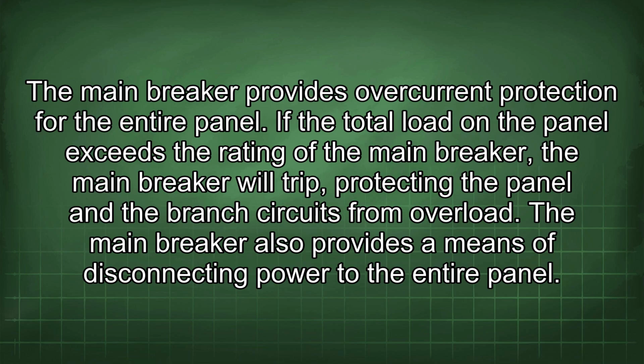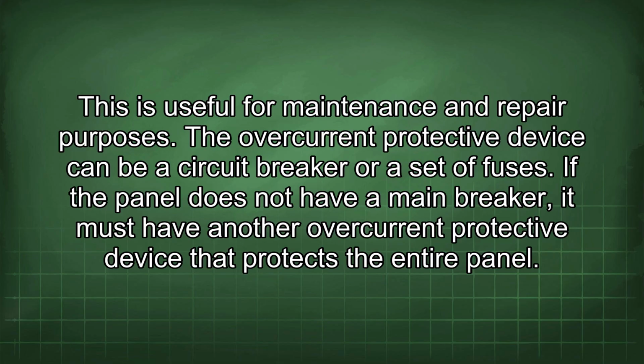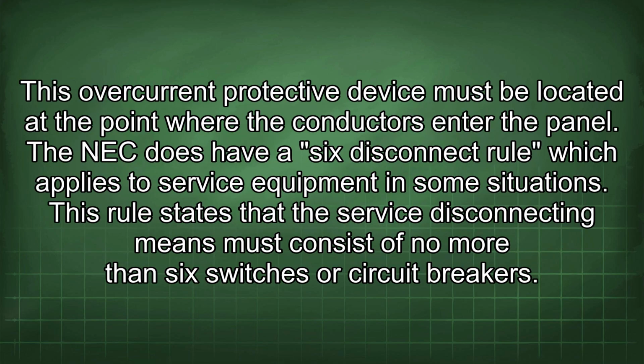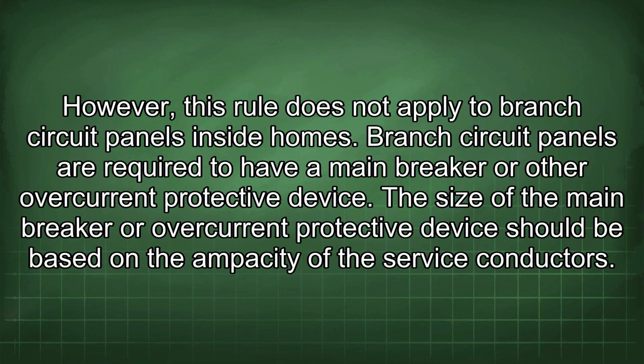The main breaker also provides a means of disconnecting power to the entire panel. This is useful for maintenance and repair purposes. The overcurrent protective device can be a circuit breaker or a set of fuses. If the panel does not have a main breaker, it must have another overcurrent protective device that protects the entire panel. This overcurrent protective device must be located at the point where the conductors enter the panel. The NEC does have a 6 disconnect rule which applies to service equipment in some situations. This rule states that the service disconnecting means must consist of no more than 6 switches or circuit breakers. However, this rule does not apply to branch circuit panels inside homes.